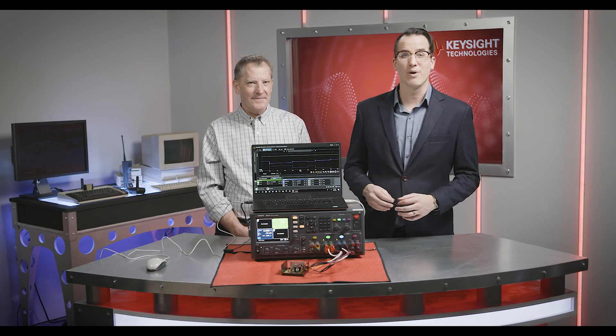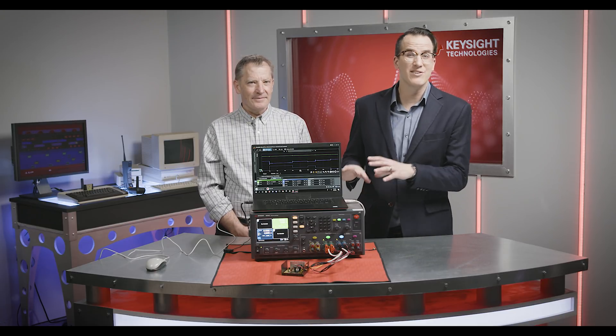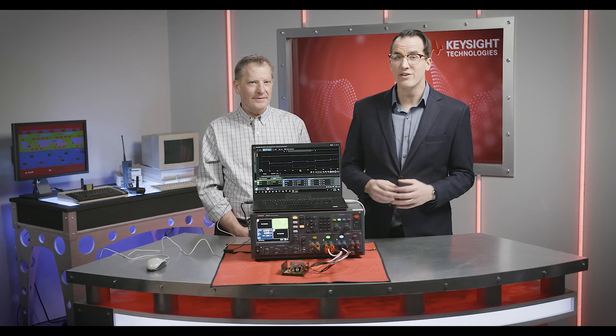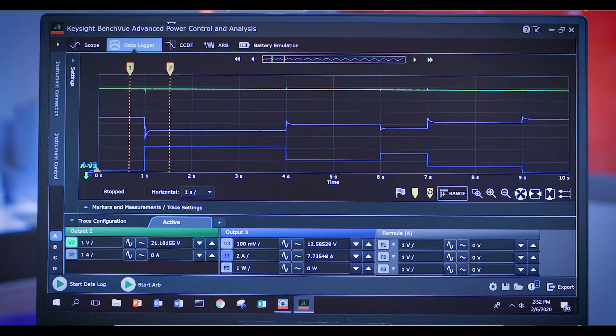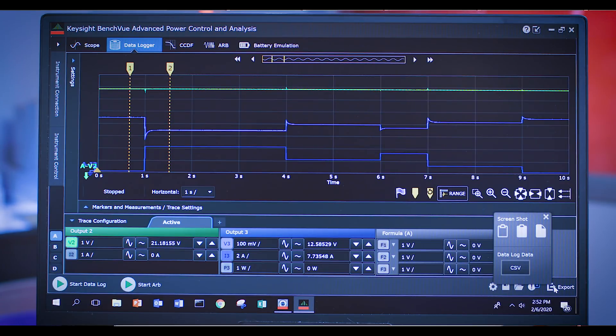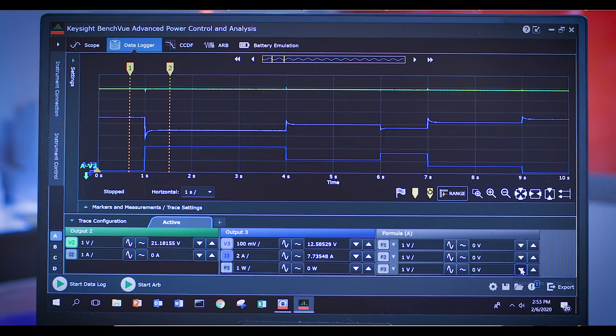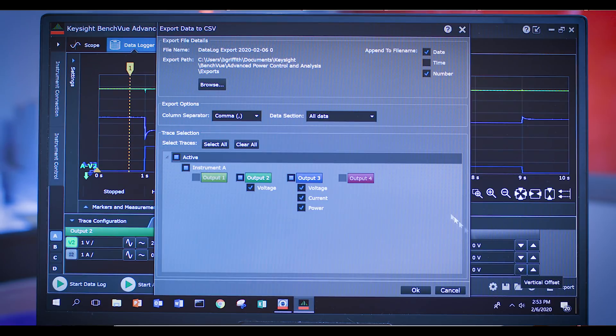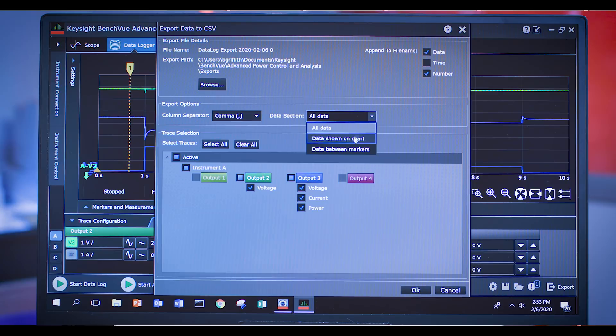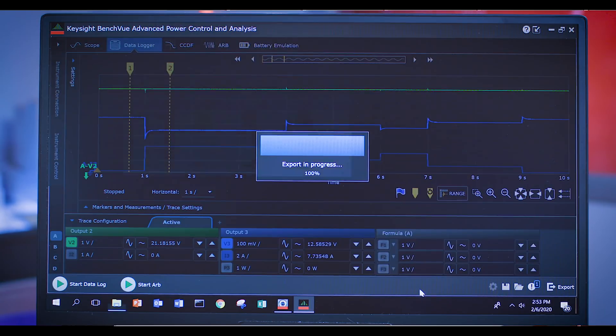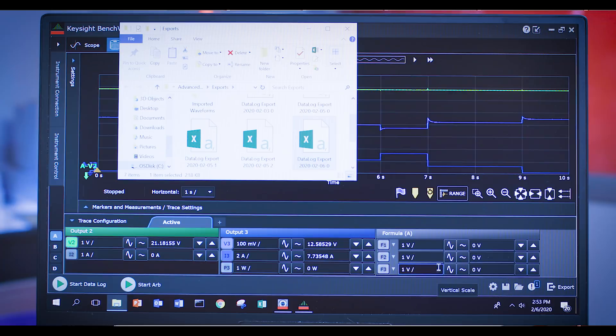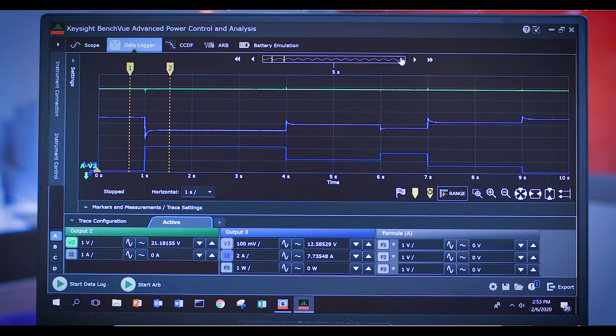The last thing to do once you have this set up is to run it for a long time. Ideally, you don't want to sit and watch it for three or six hours, so you can use data logging, which lets you set it, walk away, and come back later to see how it performs. One of the neat things they've added to the software is the ability to just save a segment of the data. We've all faced that task where we had to look through tons of data to find a certain event. Now you can set your markers around that event and just save that data.